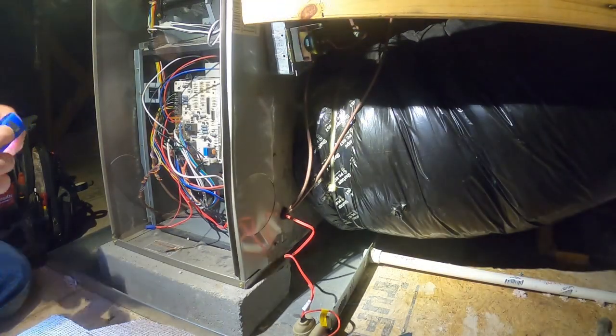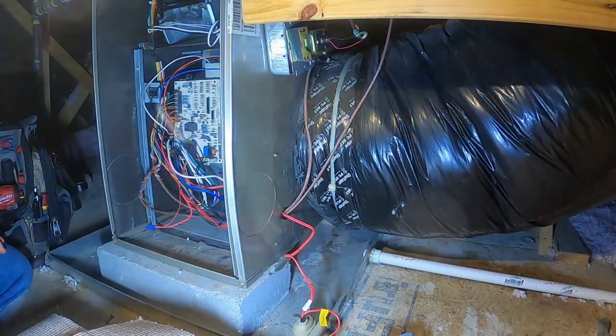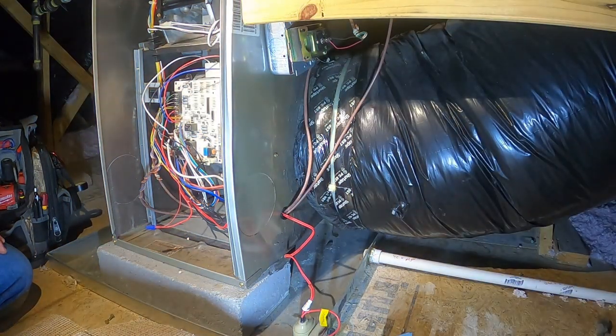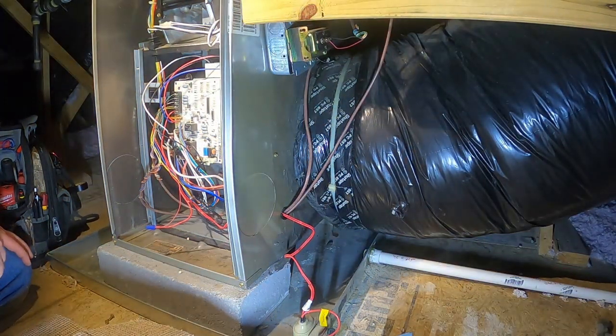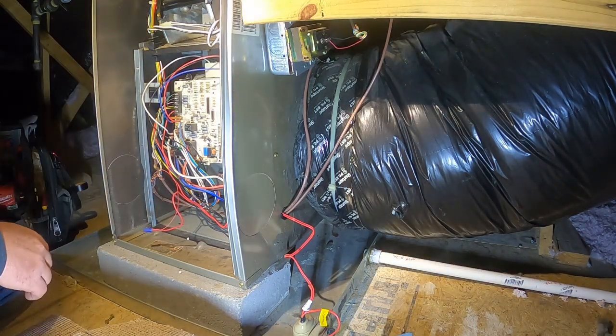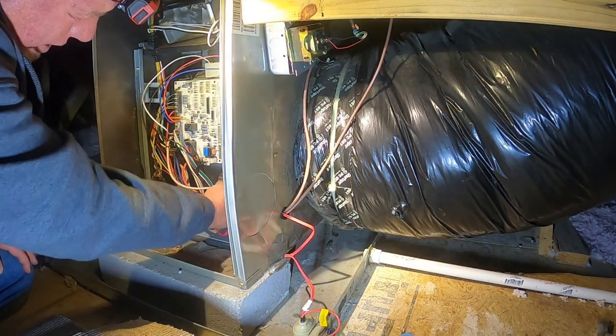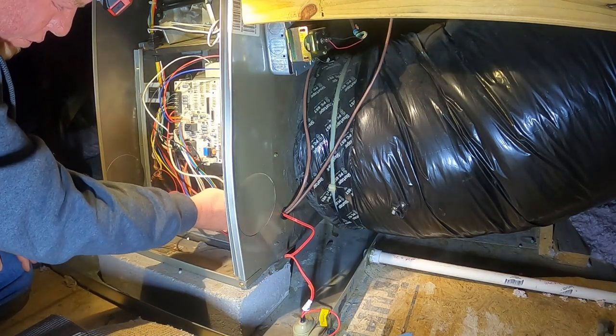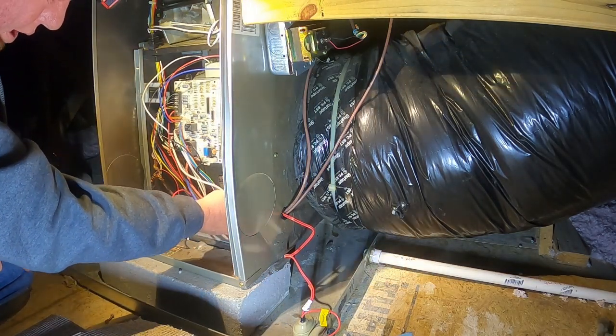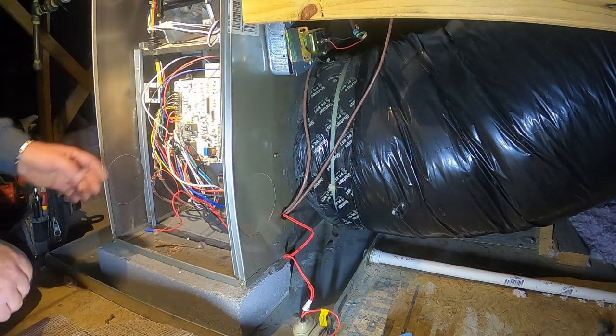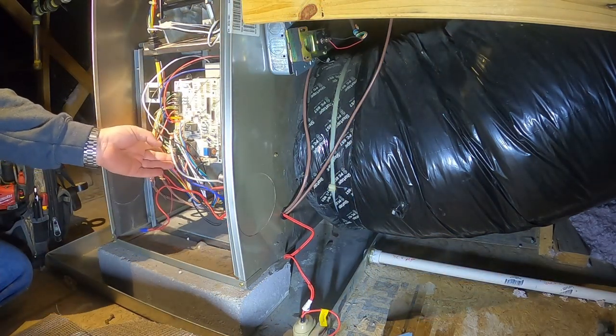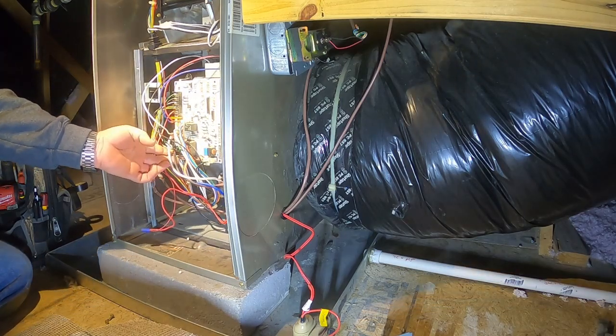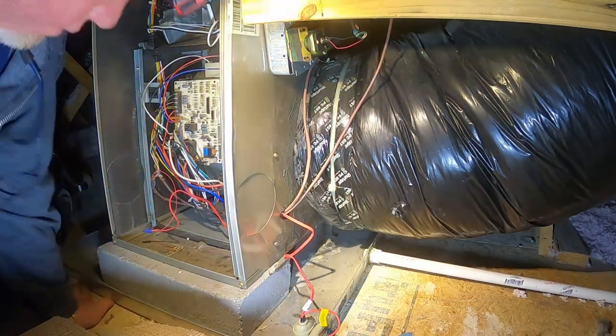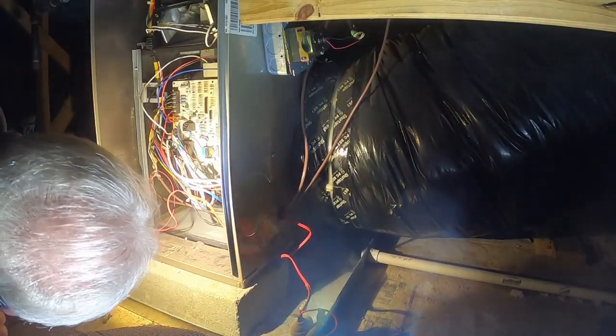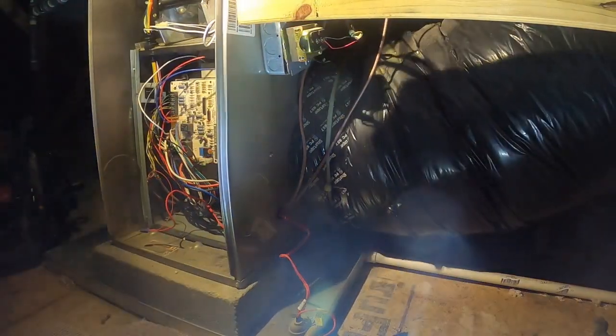Some more light out here in case I need it. But yeah, you gotta love people that just try to scam people. It's our capacitors, our brown wires, got neutral, and we got low, medium, and high basically on our speed wires. Here's our neutral. We're using our medium and high for our heating and cooling speed, and then that red wire down at the bottom is going to a park terminal, so we're not using low speed.